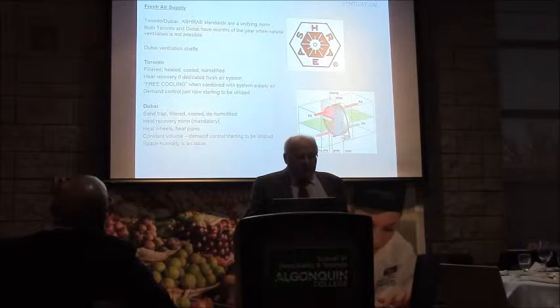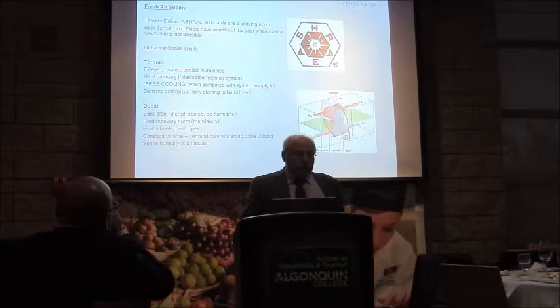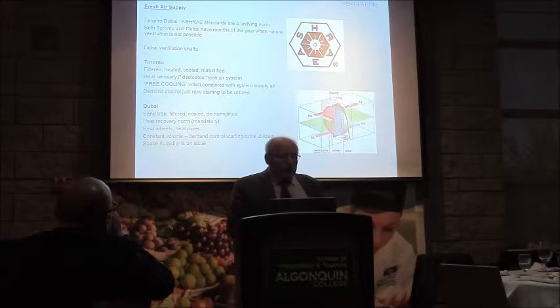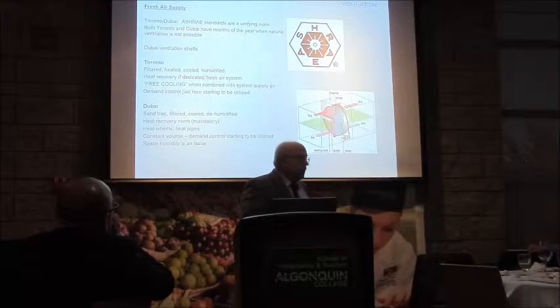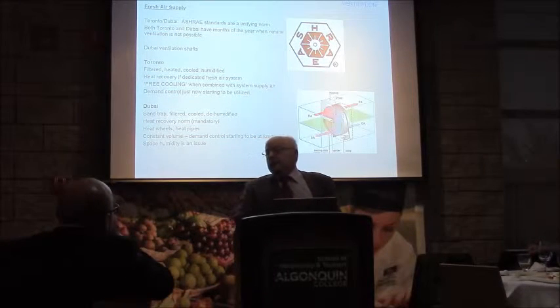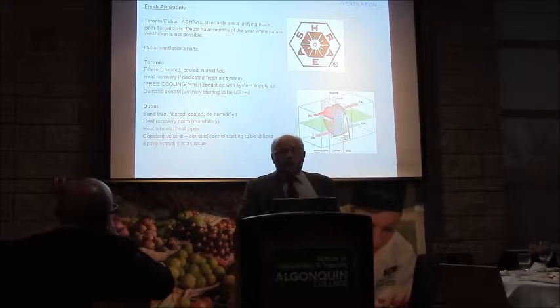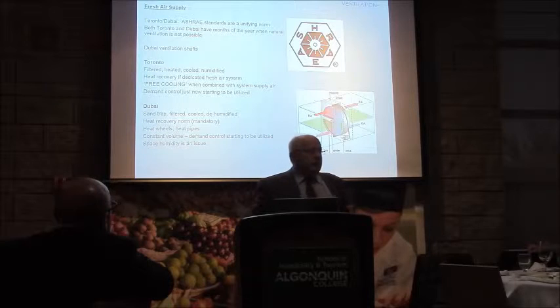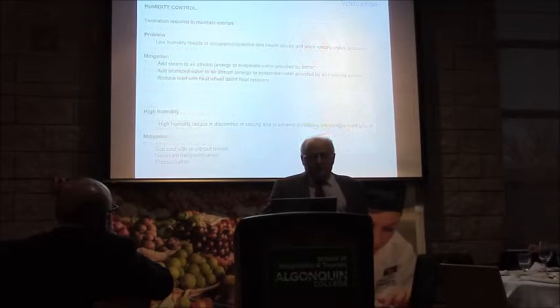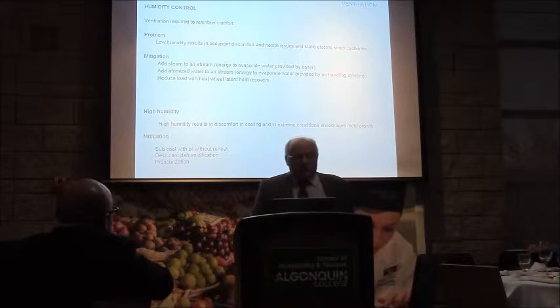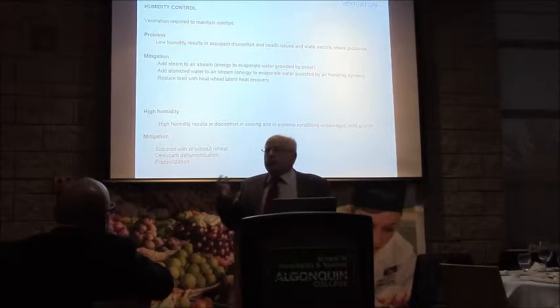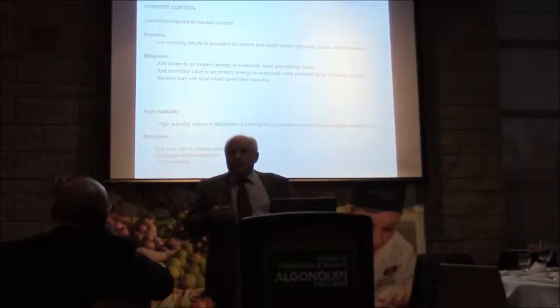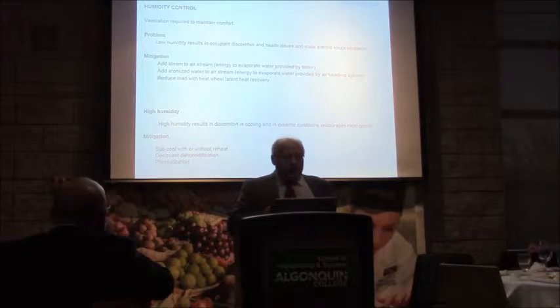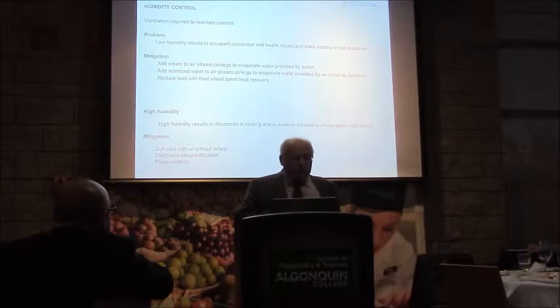Fresh air supply is an issue. In Toronto, I guess we are more and more looking to have heat wheel type heat exchange technologies. In Dubai, that's been mandated for quite a while because humidity control is an issue, and we need to do whatever we can to dry the make-up air supply. So we do need to pressurize buildings.